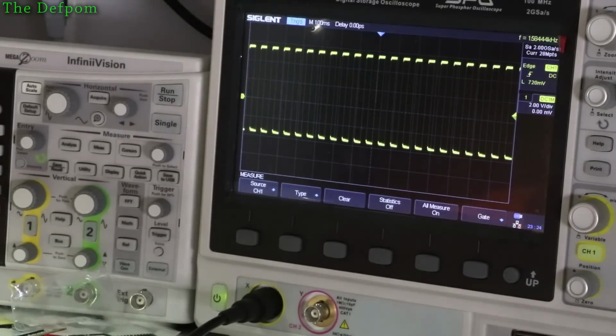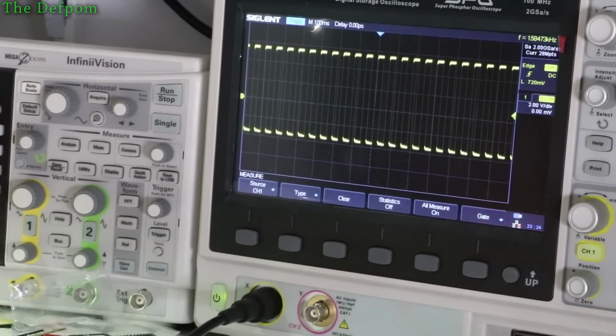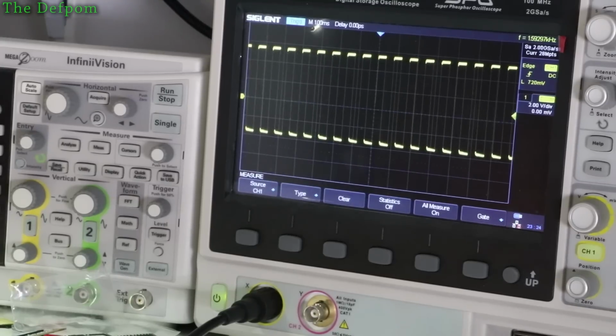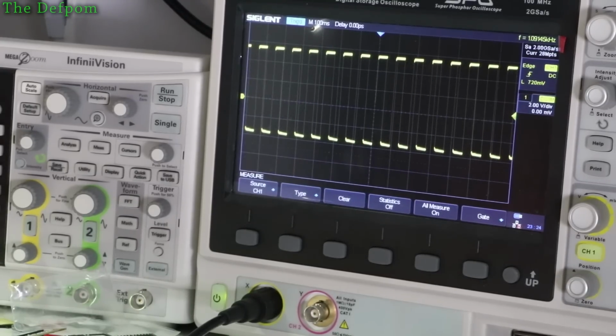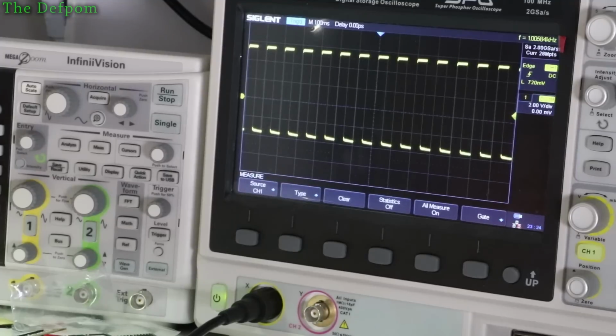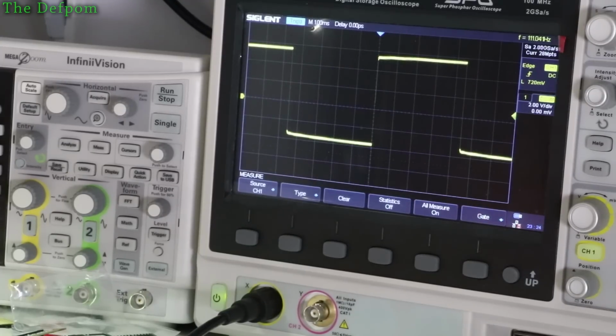I suppose I'll put 1 millisecond per division out there, and we'll see if we can get that to actually line up. So 1 millisecond is about, very close to there. So yeah, that's not where it actually has the marking on the front panel. So that's a bit different, but it's doing 1 millisecond. So do 10. It should be 10 milliseconds, but it's only doing about 5.5. So yeah, it's definitely out of calibration because it's not lining up to where it should really be.